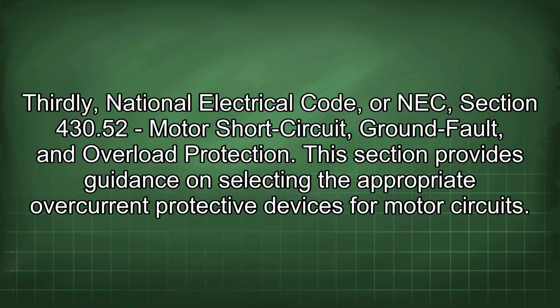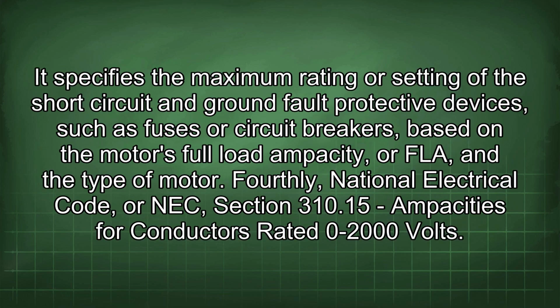Thirdly, NEC Section 430.52 Motor Short Circuit, Ground Fault, and Overload Protection. This section provides guidance on selecting the appropriate overcurrent protective devices for motor circuits. It specifies the maximum rating or setting of the short circuit and ground fault protective devices, such as fuses or circuit breakers, based on the motor's full load ampacity, or FLA, and the type of motor.